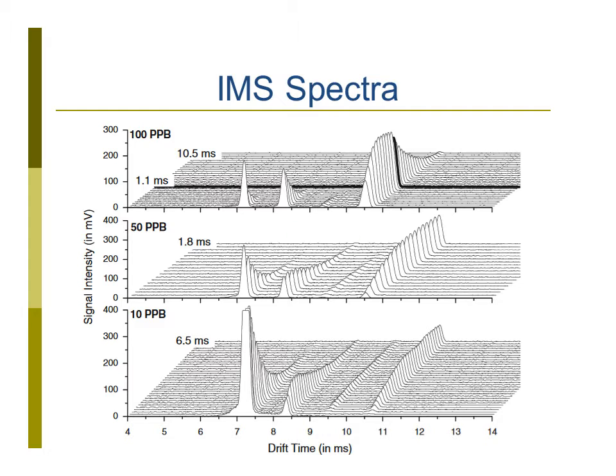This is how ion mobility spectra typically look. You always have one signal here at the beginning, which is always there. These are the so-called reactant ions, so they actually do the job and ionize the analyte that we want to detect. And then you get such spectra here, as you see. The characteristic information is after which time we detect a signal, because this time can then be used in order to calculate the mobility of this ion. And the mobility is a characteristic quantity that you can look up in tables if the substance is known, and hopefully find somewhere a value that you can use in order to identify the substance.